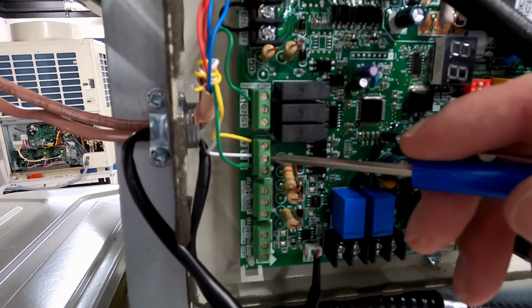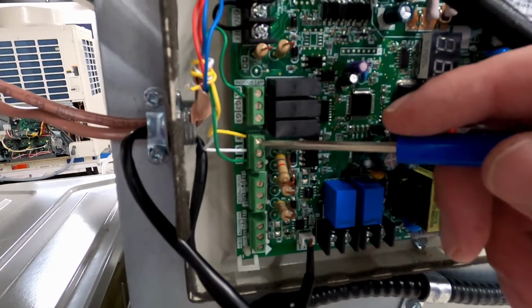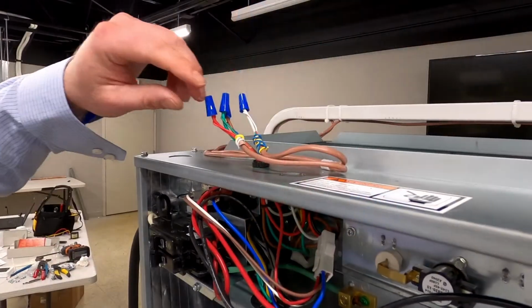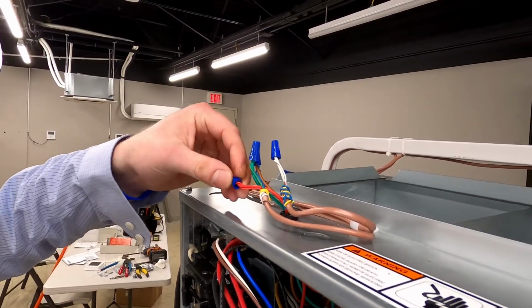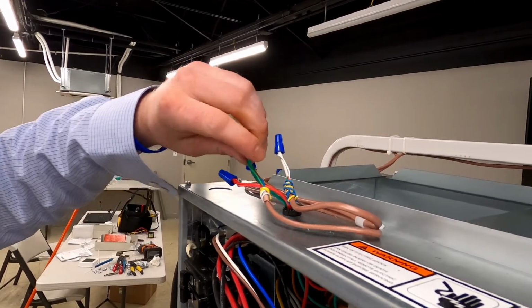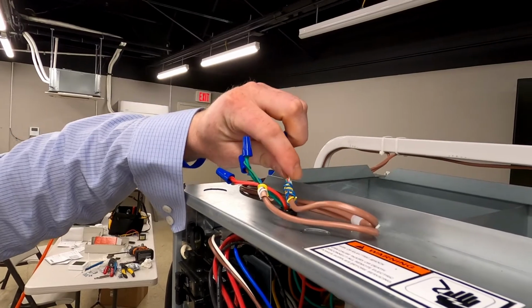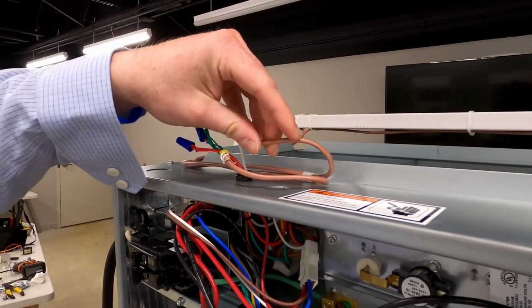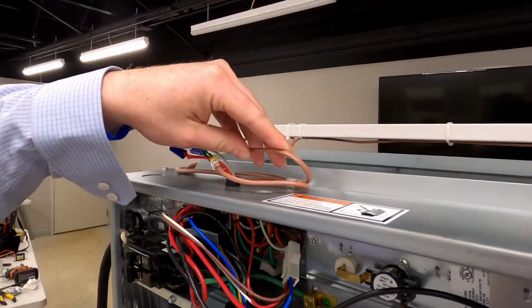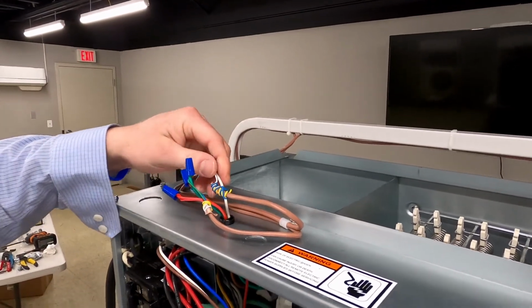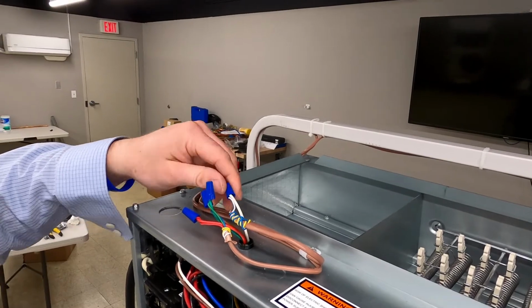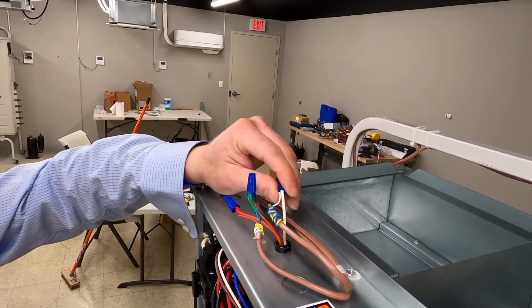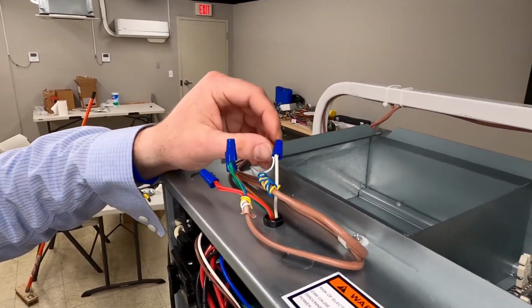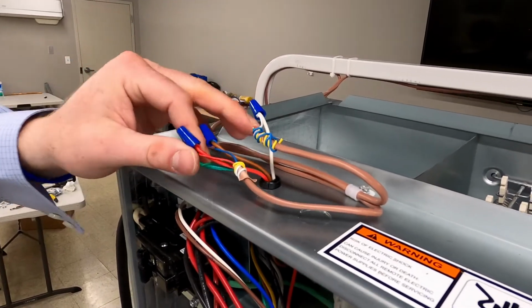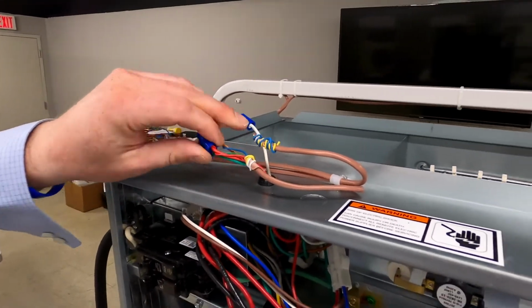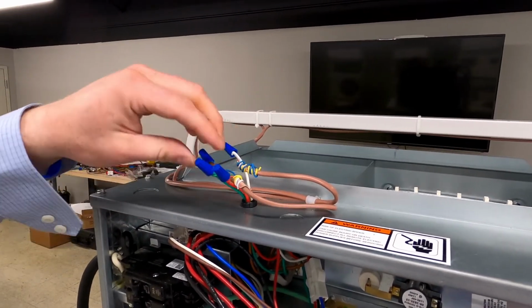Then we have our Y, W, and G, which go to the thermostat. So those are our commands for what mode we want to operate. The low voltage connections at our air handler use 4 wires. We have our R, we have our common, we have our G, and we have our W, which is for auxiliary heat. The reason that we have 2 thermostat wires over here is W comes directly from the thermostat and doesn't go through the 24 volt interface kit. So when the thermostat calls for second stage heat or auxiliary heat, it'll energize the W terminal independent of the outdoor unit or the 24 volt interface kit, which will energize the fan and the electric heater in the unit. Our other 3 wires go directly to the 24 volt interface kit. So we have our R, our G, and our common.